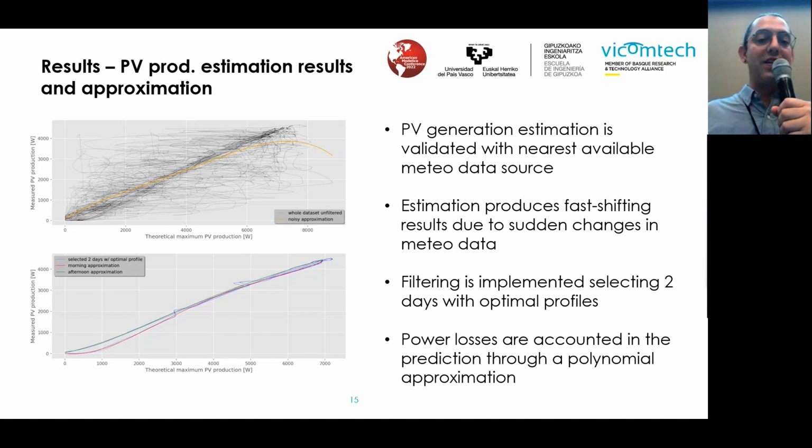So to check if things make sense, they basically did some filtering of the power profiles, and what they found is that basically the difference between the actual measurements on average and the simulation is due to the parts that they neglected related to losses on the PV part. Okay, so this basically can allow them to more or less tune and make some predictions on the available PV power of their system.